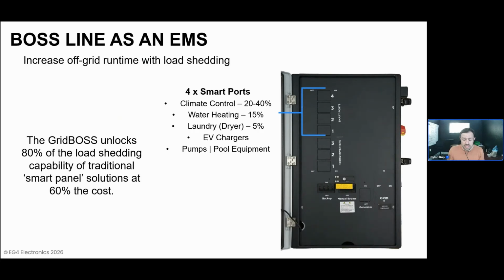Laundry equipment is another large consumer of loads. Any resistive heating generally will be a heavy consumer. And then certainly special considerations, things like EV chargers or pool pumps can become energy hogs where those are deployed. They're not across every home, so they're not usually represented as well in the data, but certainly we know from experience, those can become very energy intensive devices, and so make a lot of sense to intelligently manage those and load shed those under certain conditions to really prolong the performance of that system.